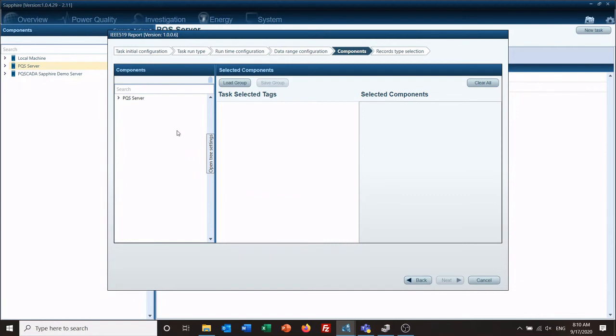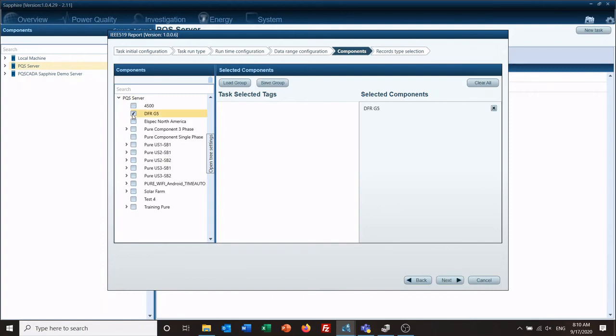Here is where you select which device is going to provide data for this report. Make sure it's one that is always on, that you're connected to, and that you don't have any problems with. If you have many meters being added regularly, you can use the tagging system to create tags — you'd only have to build this once and then add the tag to each new meter. We discussed tagging in one of our previous quick tip videos. For now, we're just going to select the one component we want this report to run from, and select next.